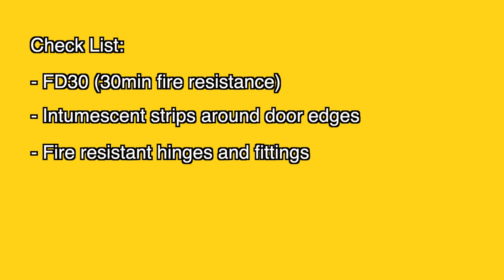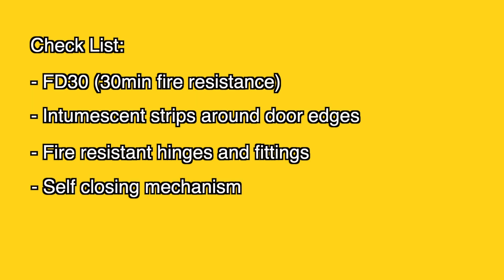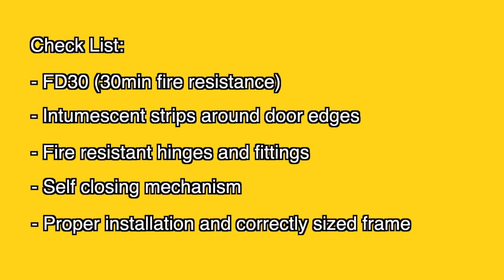Let's recap. Here's a quick checklist for fire doors into garages: FD30 with a 30-minute fire resistance, intumescent strips around the door edges, fire-resistant hinges and fittings, self-closing mechanism to ensure it's always shut, and proper installation with a correctly sized frame.